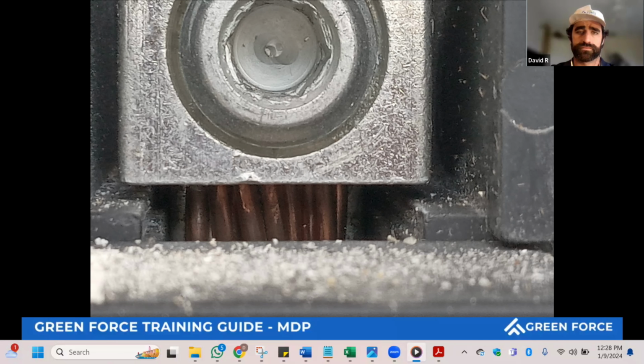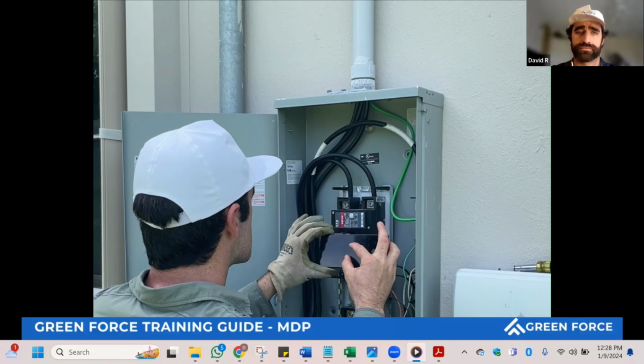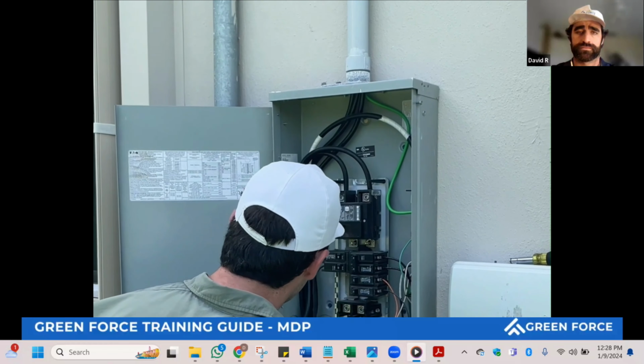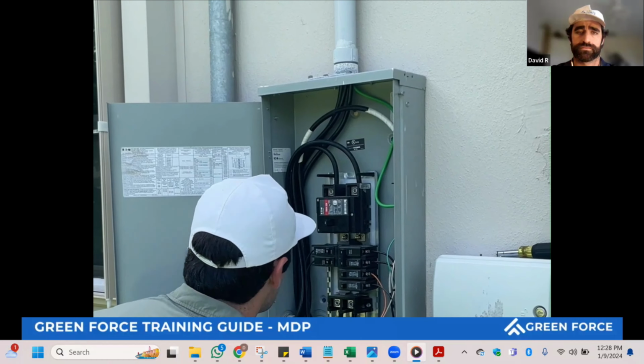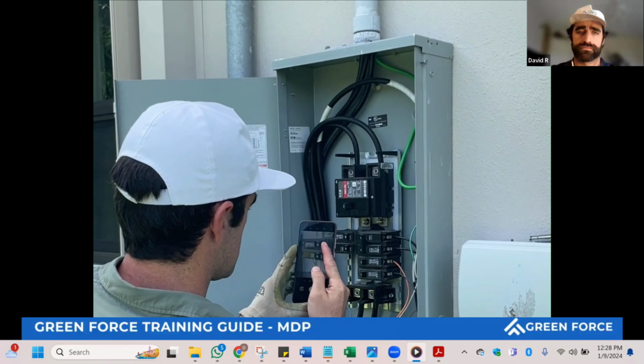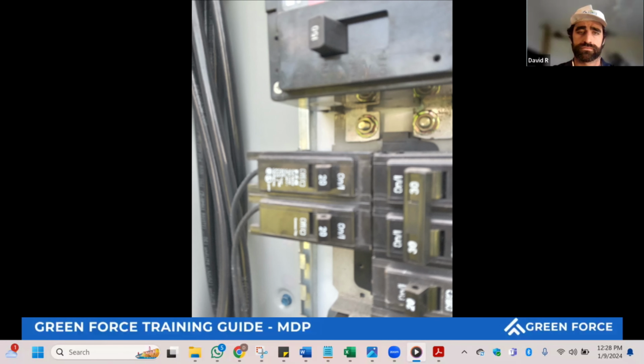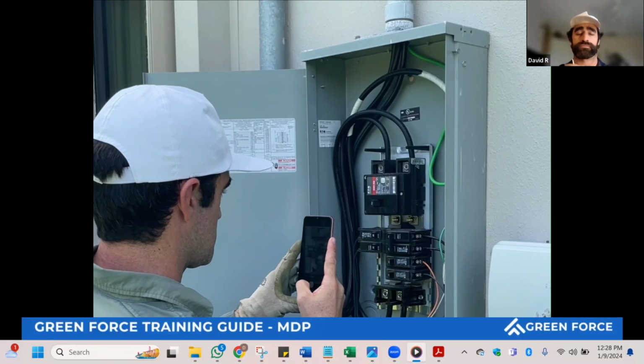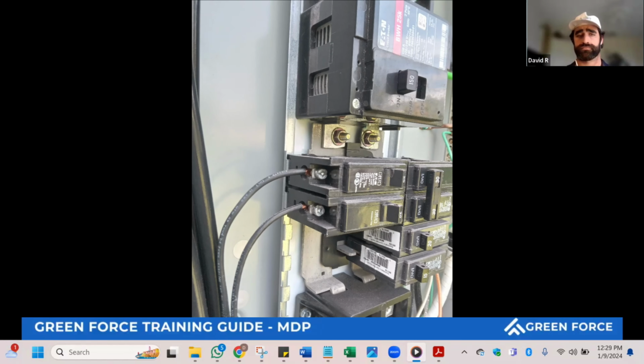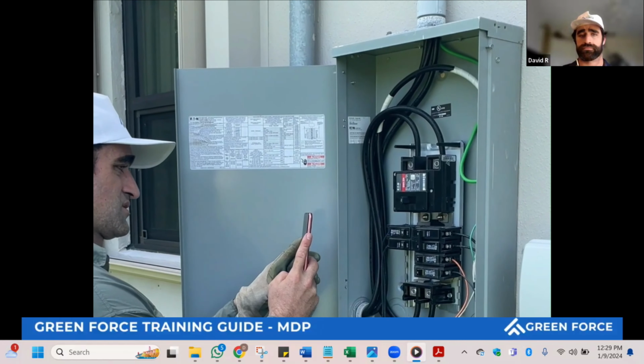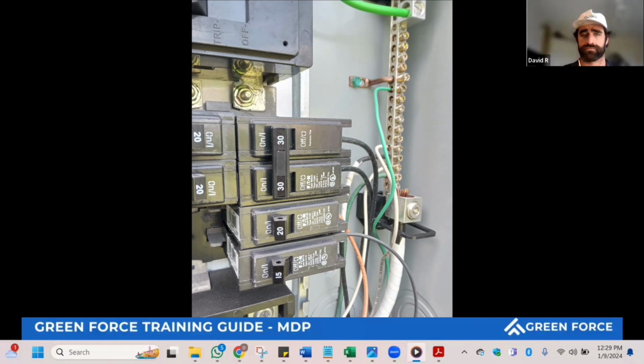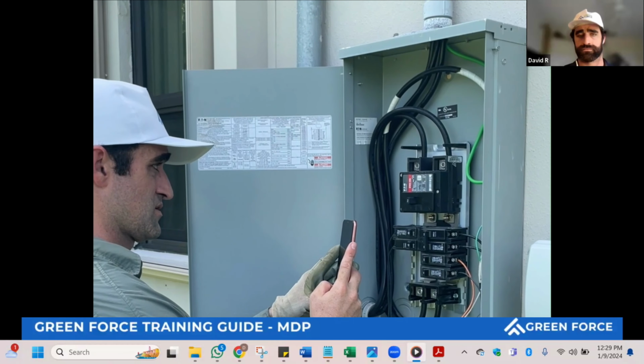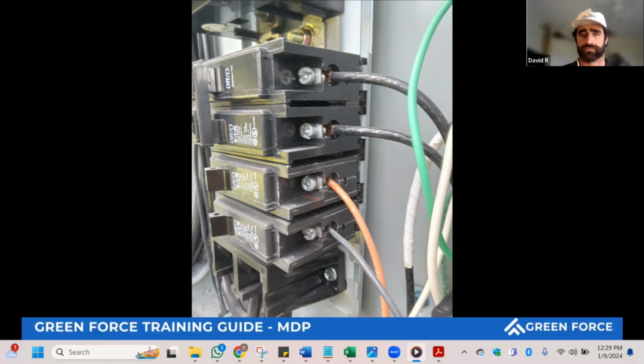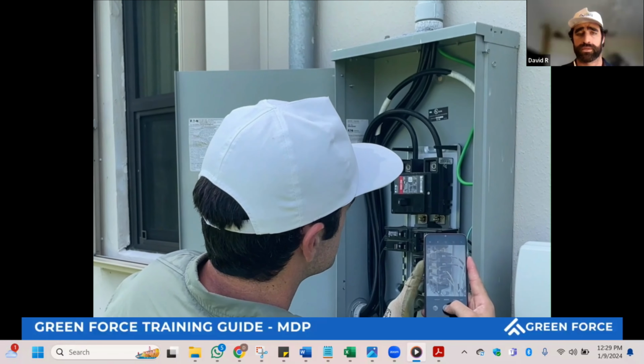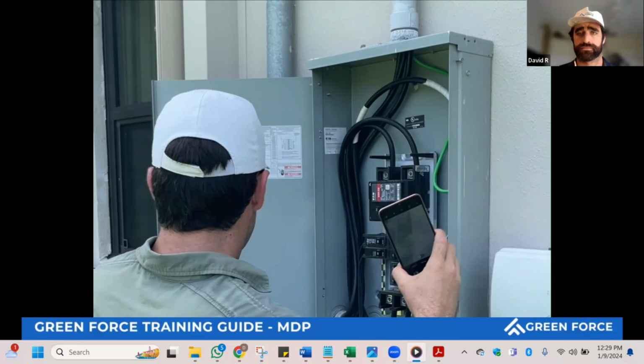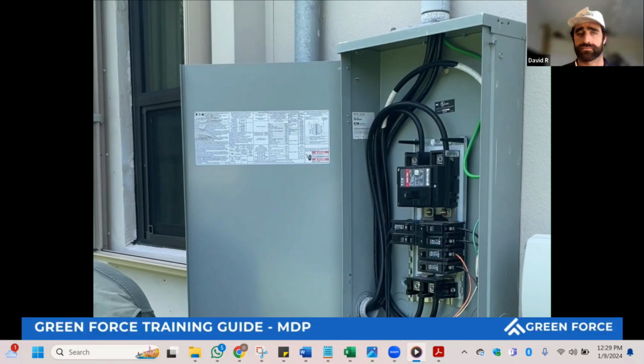Inspect the material of the line-side conductors of the MDP, documenting their condition and material. Photograph the breakers on the left side of the panel and the wires entering them, then the breakers on the right side and their respective wires. This detailed inspection unveils the intricate wiring of your electrical system, shedding light on its reliability.